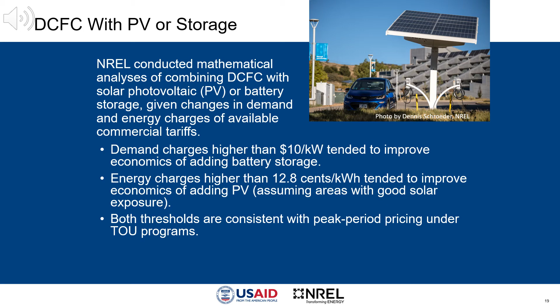The profitability of DC fast charging is especially sensitive to the balance between energy costs and demand costs. Two things have made that balance easier to manage, however: improvements in battery storage and lower costs for solar power. NREL studied how storage and solar might affect the economics of DC fast charging using commercial tariffs in the United States. The analysis found that demand charges higher than $10 per kilowatt tend to make adding battery storage more reasonable. It also found that in areas with good solar potential, energy charges higher than 13 cents per kilowatt hour tended to improve the economics of adding PV panels to the charging station. Both of these thresholds for demand charges and energy charges are consistent with peak period pricing under a typical time-of-use commercial tariff.